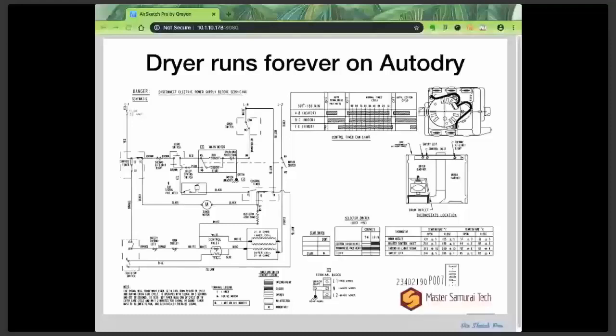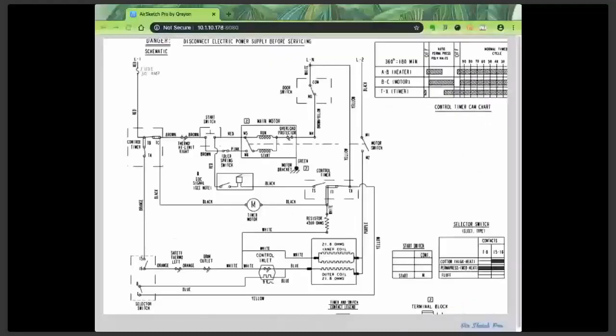Remember, a load is the thing that actually does something in the physical world, and it's all about watts—motors, heating elements, lights. So the load of interest is the timer motor. Not just the timer—a mechanical timer has two parts, the contacts, and if you want to include it, the cam that moves the contacts. Those are the various contacts you see up here; those are timer contacts, just switches, and the timer chart tells you which switches are open or closed in the cycle. But the actual part of the timer you need to narrow in on is the timer motor itself.